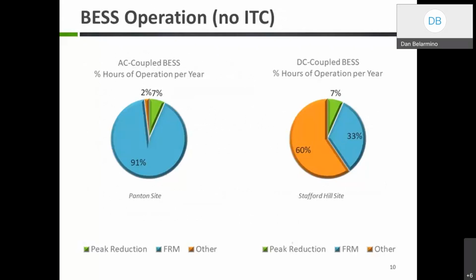Here at the Panton site, an AC coupled system, about 7% of the time, or 25 to 30 times a year, we operate the battery for peak reduction, to hit the forward capacity peak and regional network services. About 4 times a month in June, July, and August, that's when we hit the FCM peak, and we also operate the battery about 1 to 2 times a month in other months for regional network services.